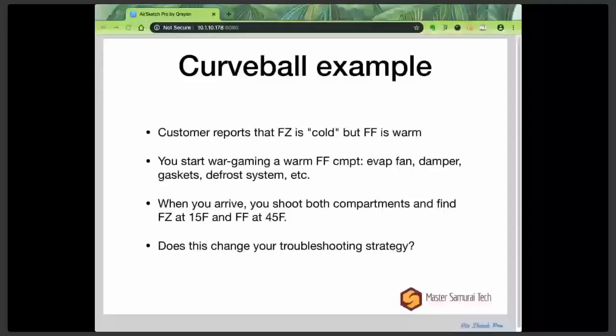So if I see something below 20, for example, I have a problem. It's like an Ohm's test in that case. If the Ohm's test is bad, in other words open, or shorted when it shouldn't be, then yeah, I found a problem. But if the ohms are in spec, I haven't necessarily found a problem.